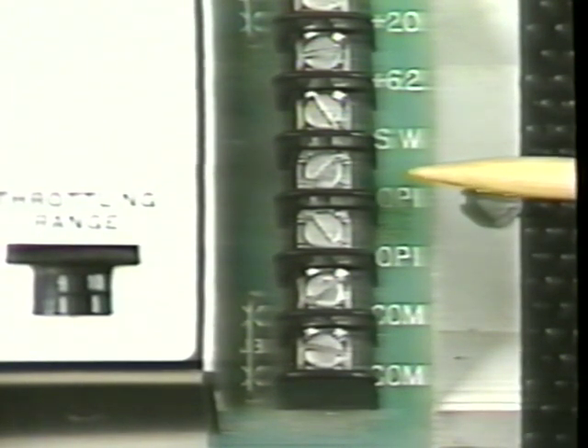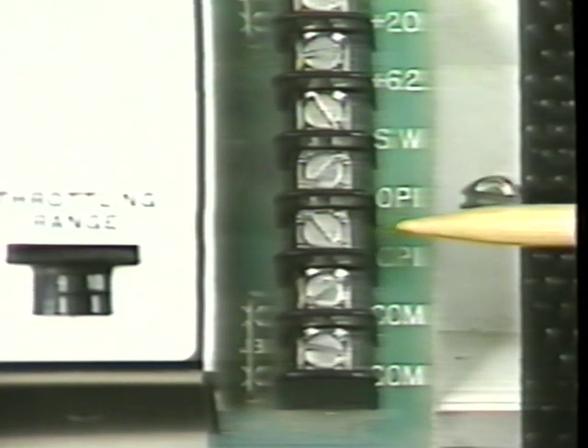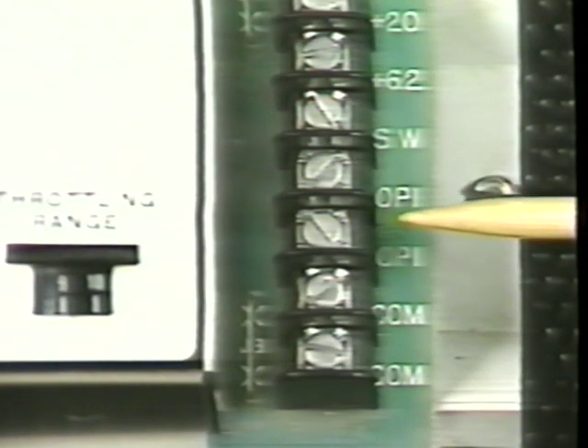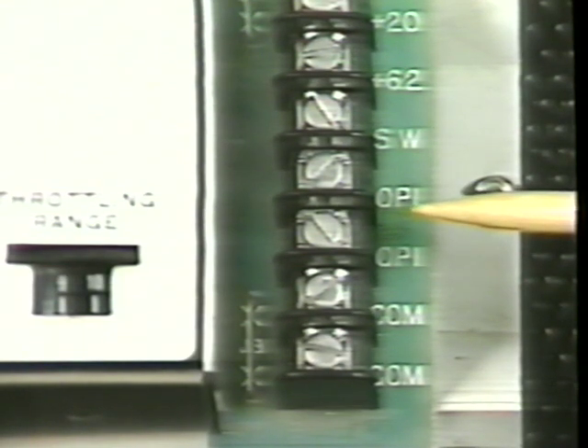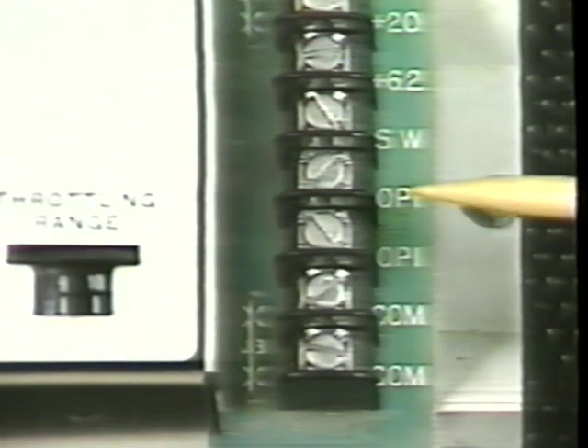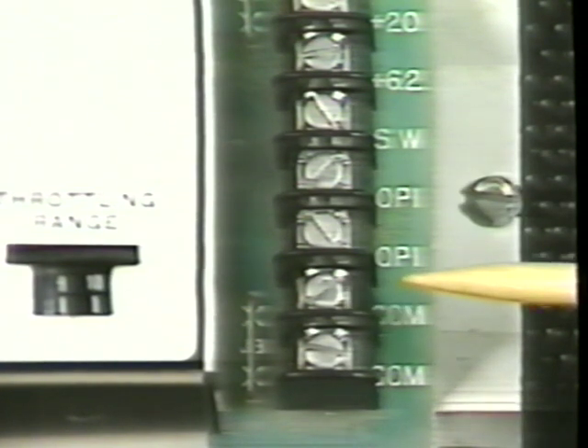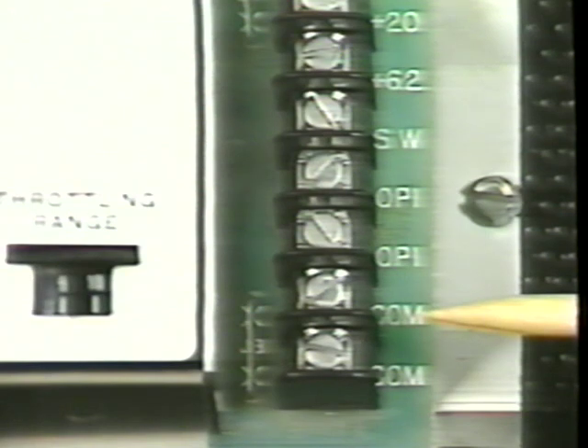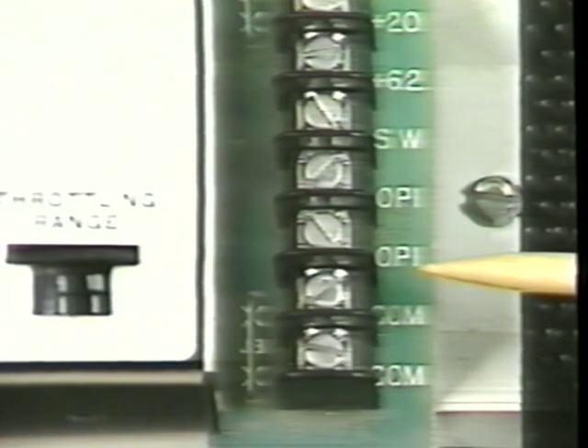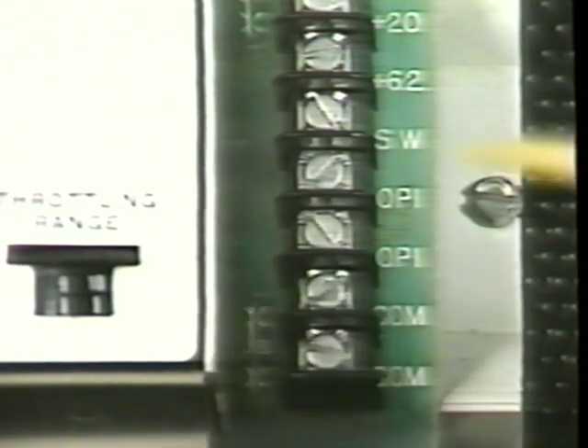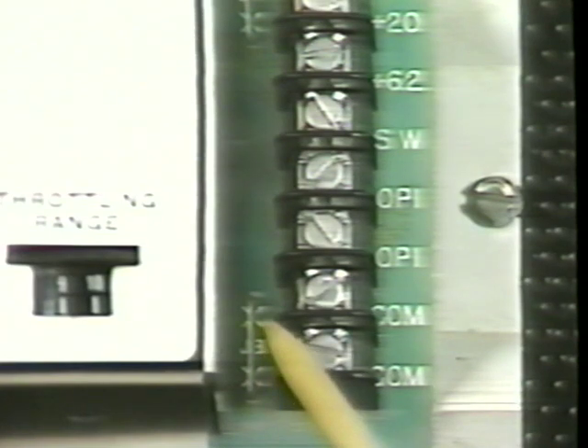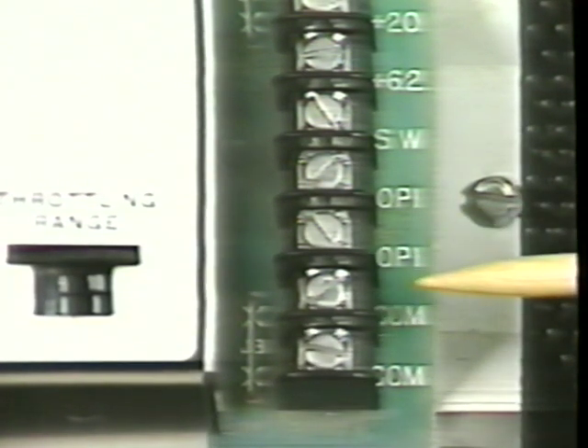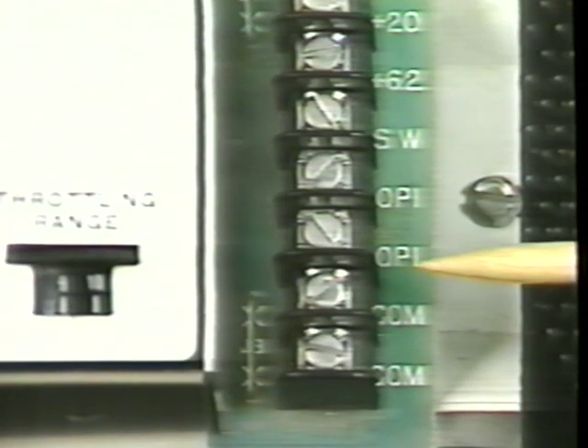OP1, 2 identical output terminals. The output is a 1 to 15 volt DC controller signal. Up to 6 System 8000 controlled devices can be operated directly on this signal. And common. These 2 terminals serve as reference for the various positive voltages already referred to. The upper common can be isolated by cutting jumper strap J8 located here, and is then usable for controller switching, as was mentioned for the SW terminal.